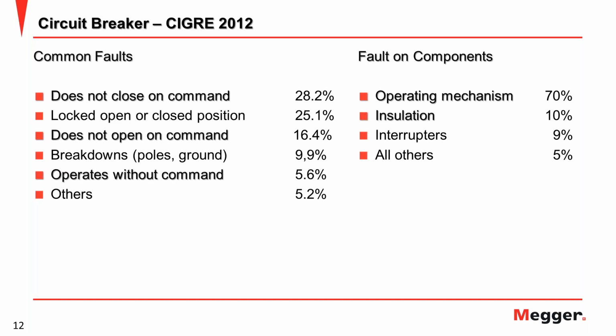So I think some information is very relevant to the MV circuit breaker, like does not close on command, and also operate without command, mostly because it gets a trigger from external, like maybe a relay suddenly works, gives a trigger to the breaker and then the breaker operates, or does not open on command. So these three common faults, I think, are relevant to the MV circuit breaker.